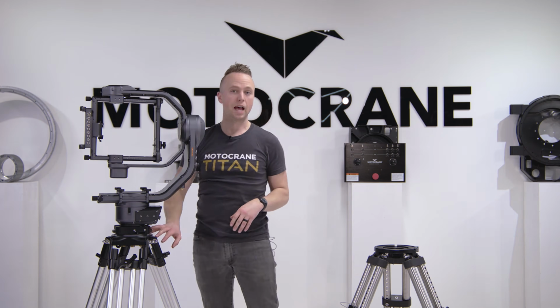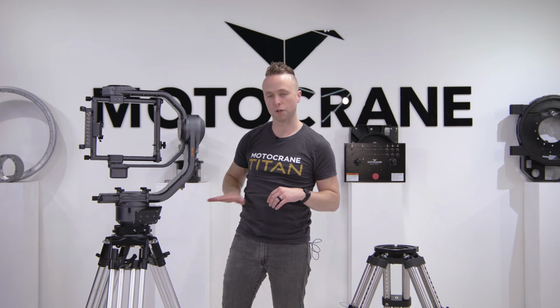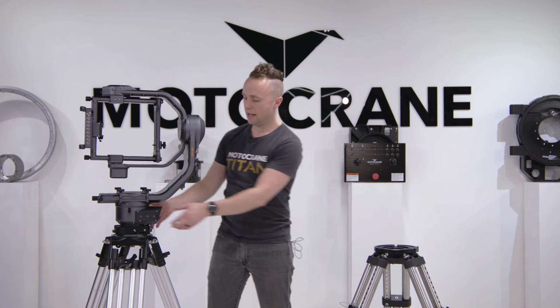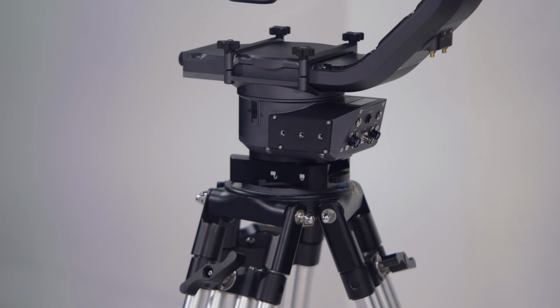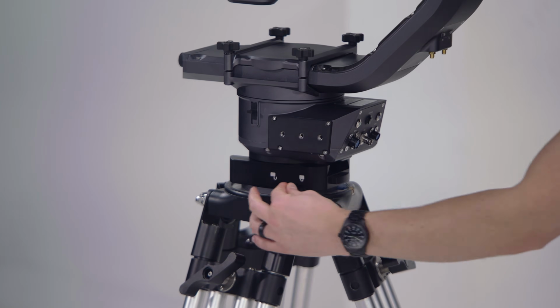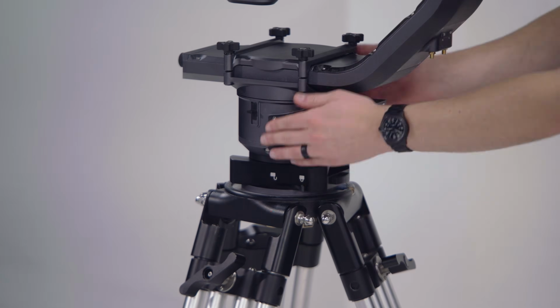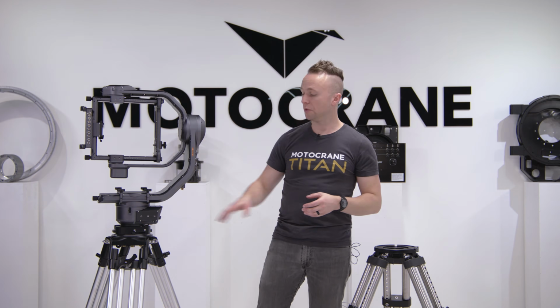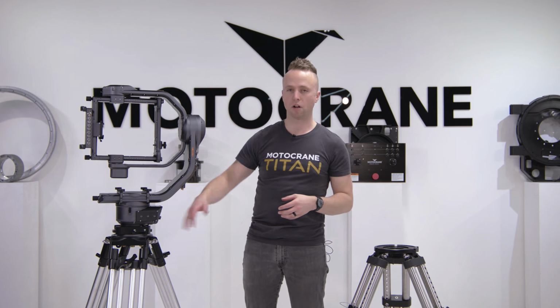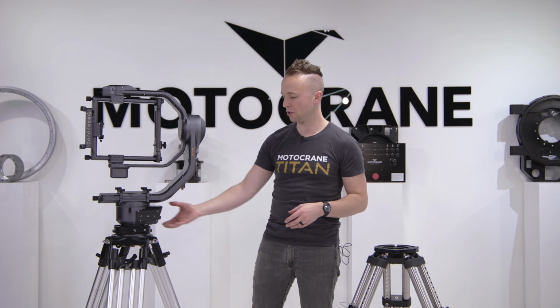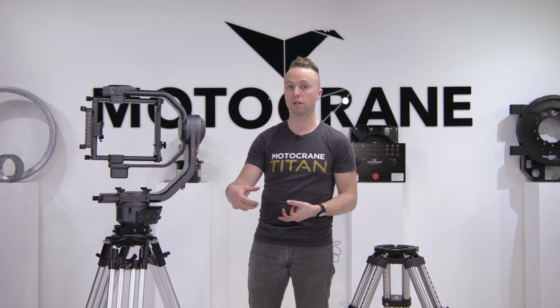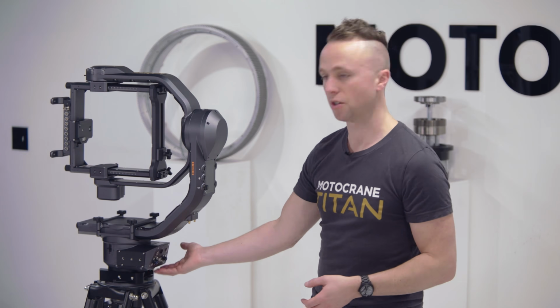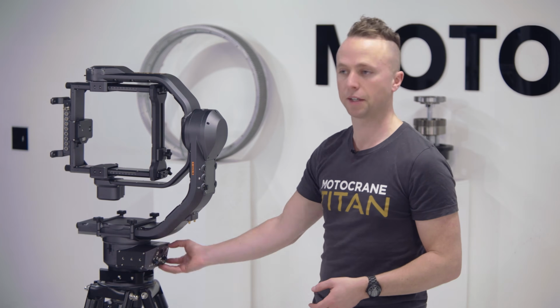The quick disconnect has 2 sprung latches so that when fully installed, you'll hear a click and it can't come back out. Then we'll move our locking lever to the locked position to make sure there's no play in that dovetail. When using the LT quick disconnect, you can install LT from either side, just note that'll change the orientation of where your connectors are coming. I have it installed this way so we can see and install the connectors from this side.